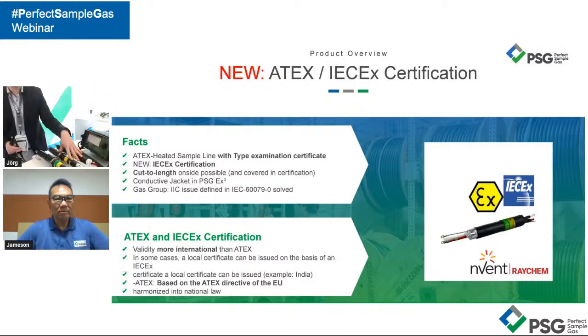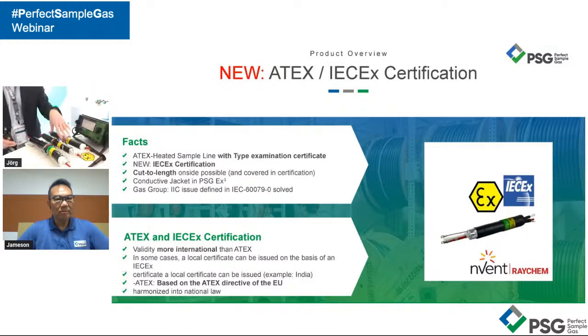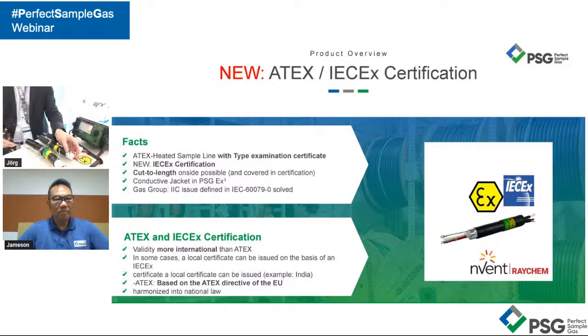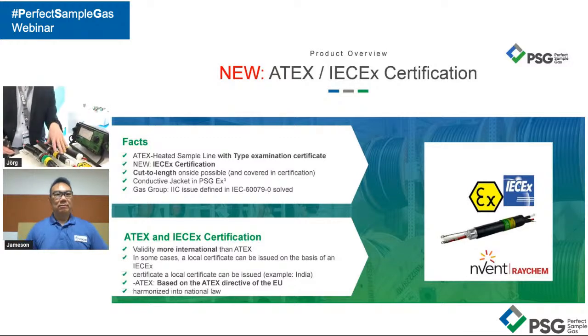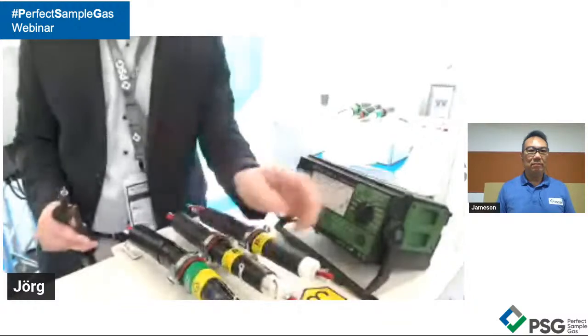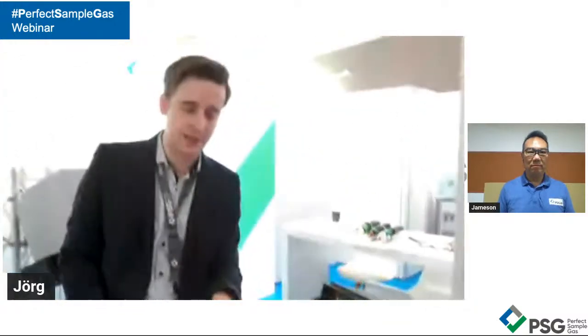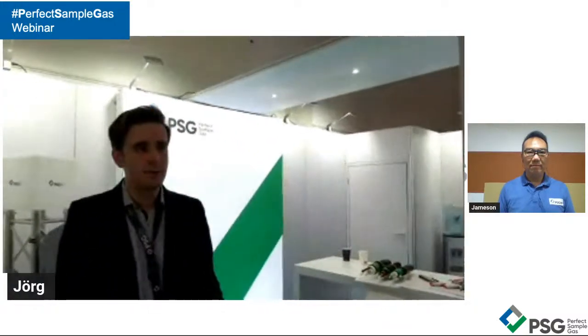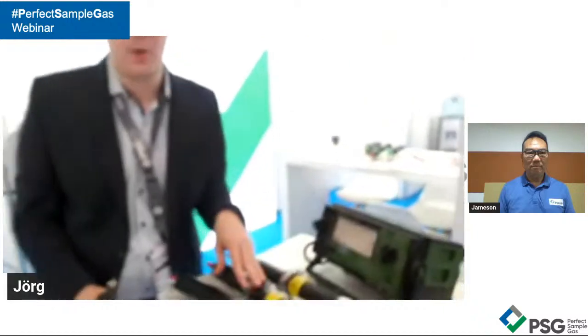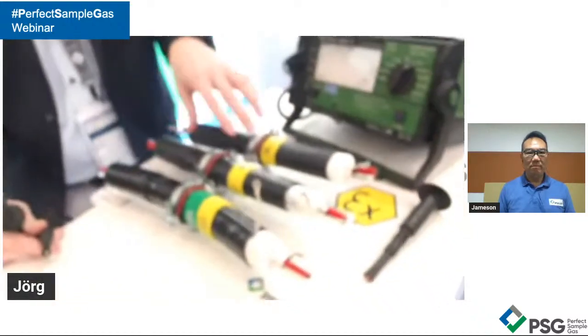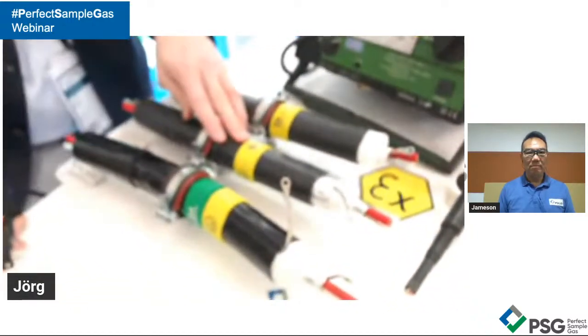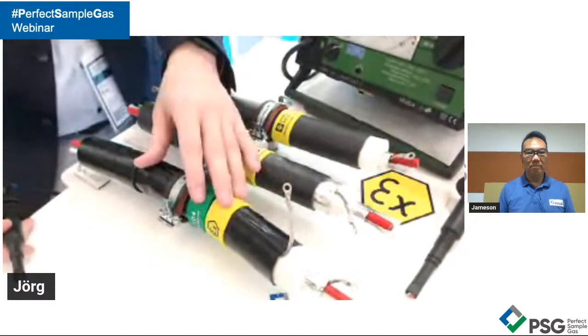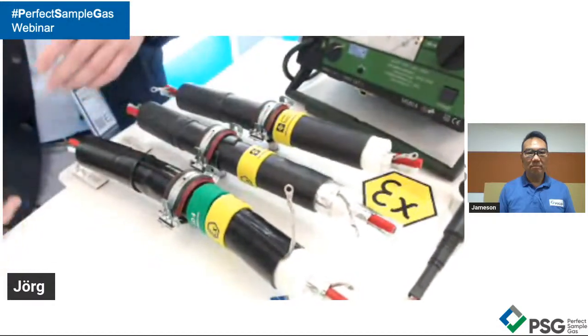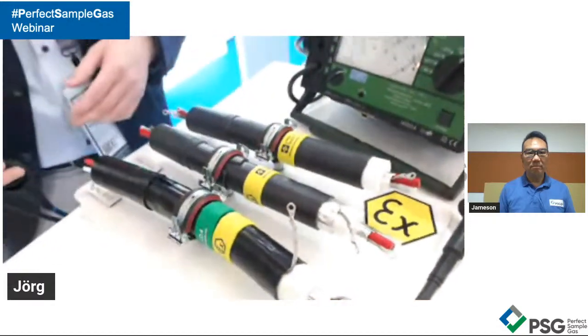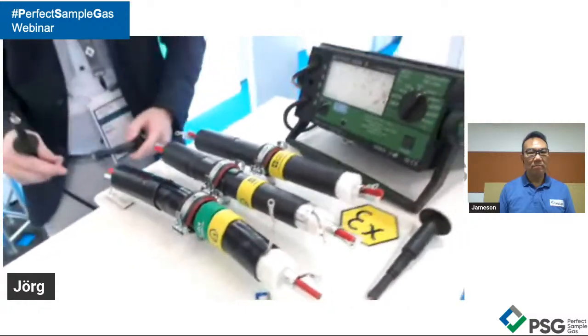One of them is our X2 line, ATEX to the power of 2. It is not conductive itself, but it has a layer of aluminum foil just beneath the jacket. This means if static electricity builds up, it can flow through this aluminum foil layer to protective earth. It is suitable for zone 1, zone 2, and almost all substances except hydrogen and acetylene. So we also have a solution if you are using those, or if you just want to be on the safe side.